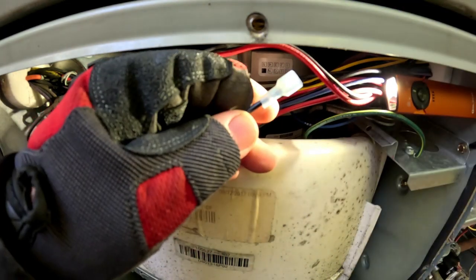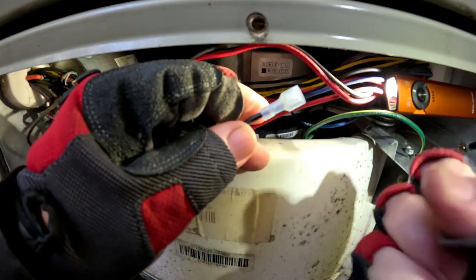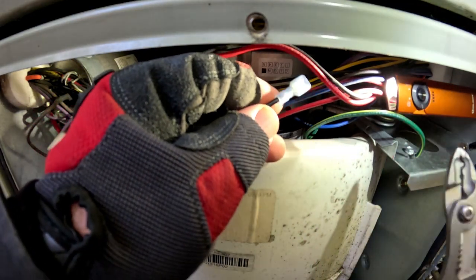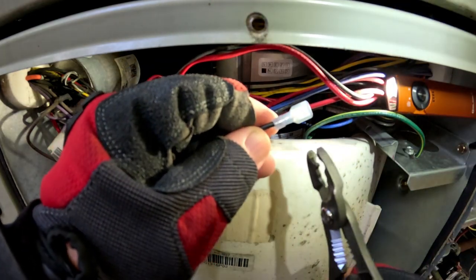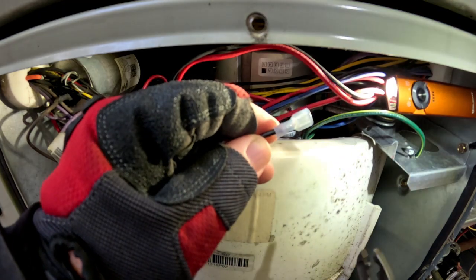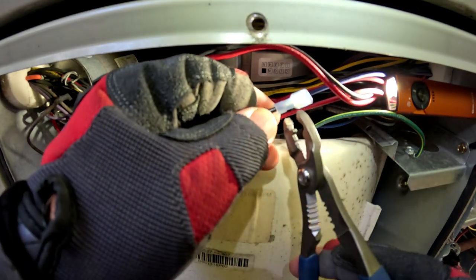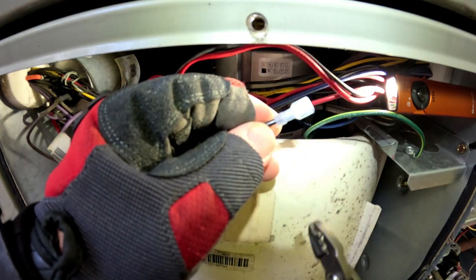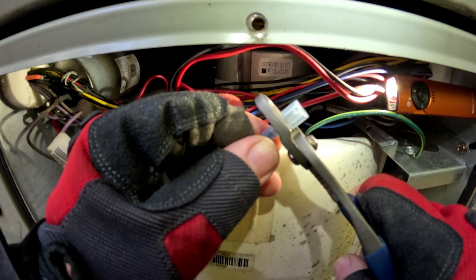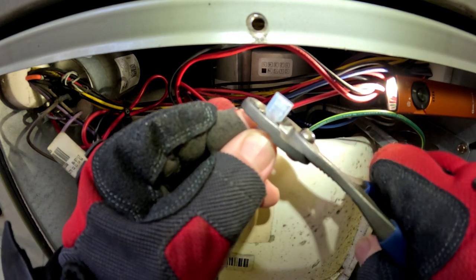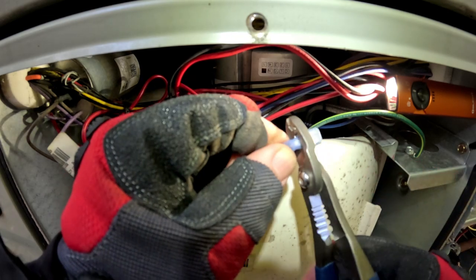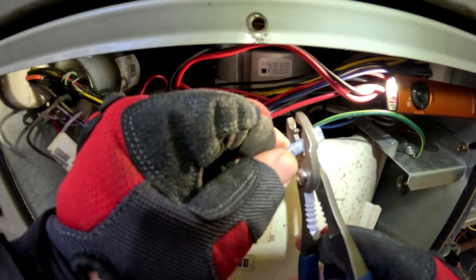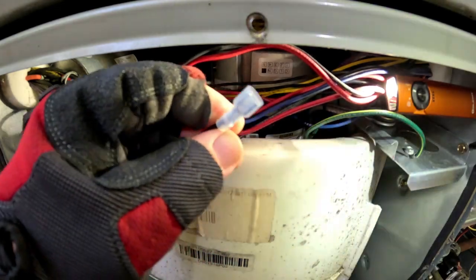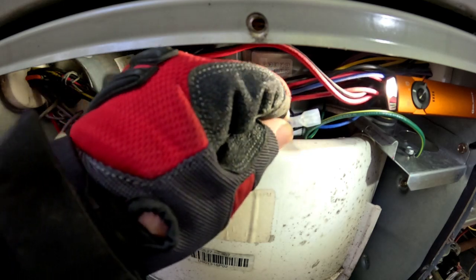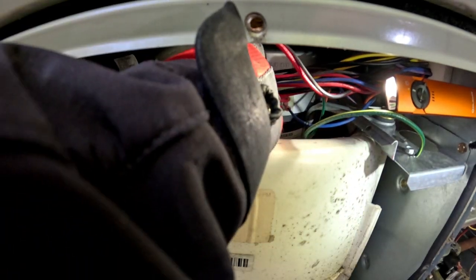So last time this motor housing was slid out, if you're familiar with these package units, you'll know that all these wires are zip tied real tight together. So you've got to cut the zip tie and get the wires apart to slide this out if you're going to check the heat exchanger, or try to get back there and clean that coil or whatever you're doing. When you put it back in, you have to zip tie all your wires back together, or they are going to end up in that blower wheel, and then we're going to have a problem. So, all right, let's plug that back on here.